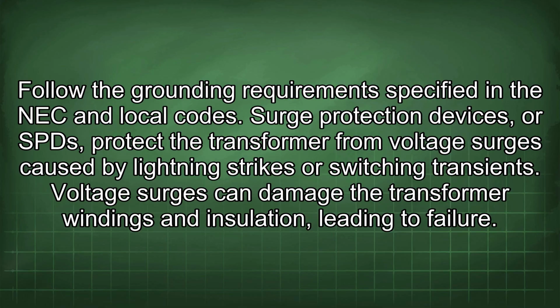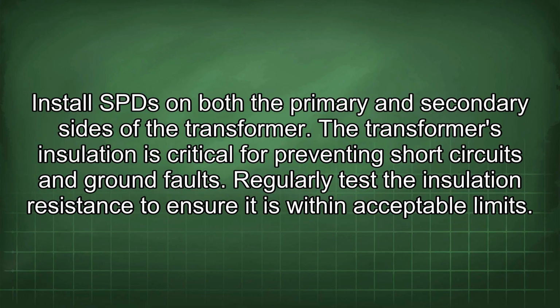Surge protection devices, or SPDs, protect the transformer from voltage surges caused by lightning strikes or switching transients. Voltage surges can damage the transformer windings and insulation, leading to failure. Install SPDs on both the primary and secondary sides of the transformer.